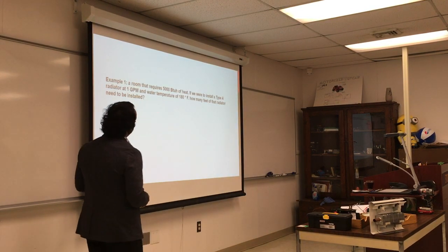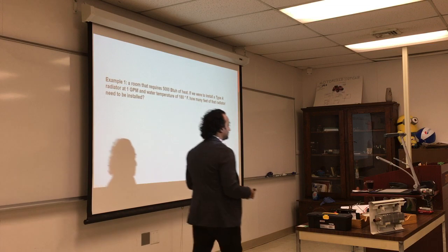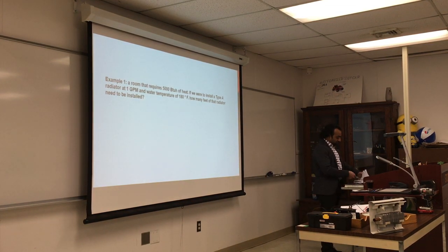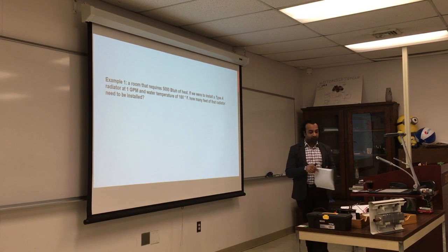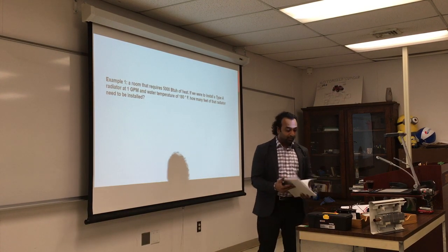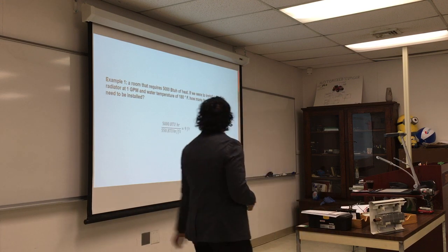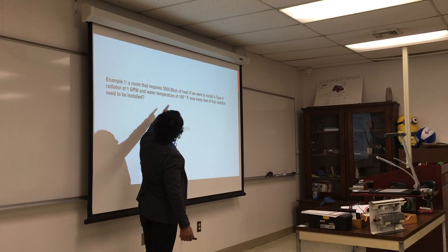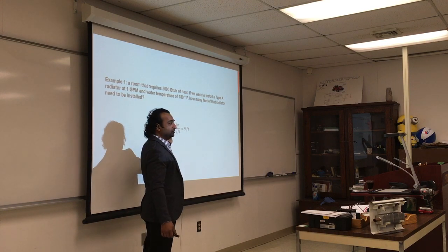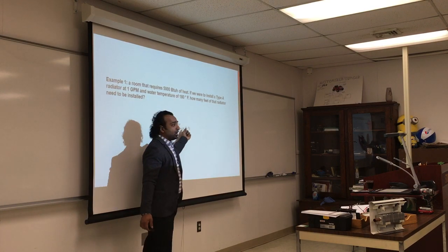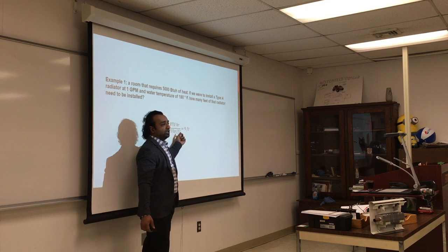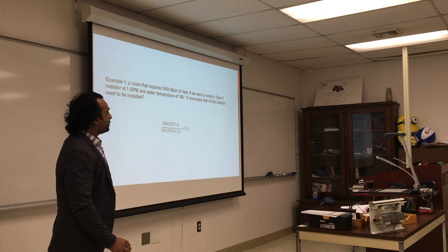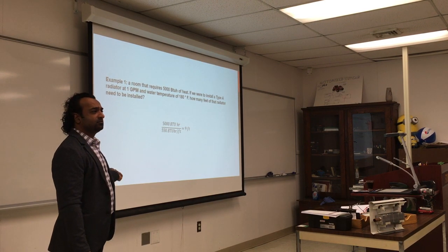And we had this example. I would say it's a straight look up from the book. It will be very helpful if you can locate your table in the book so you can follow through. And there are a few examples worked out in the book. And we said if we look up that water temperature at 1 GPM, type A at 550 BTU per foot, now we know how many feet we need for that radiator. Any question about that? Does it seem straightforward?